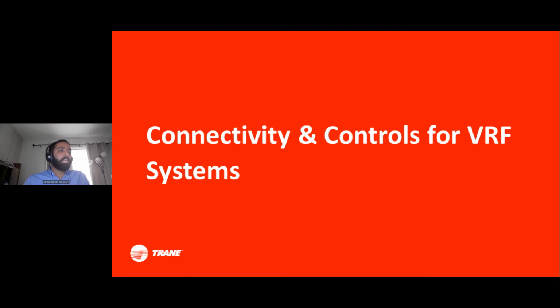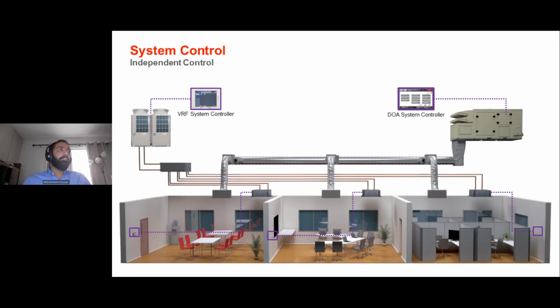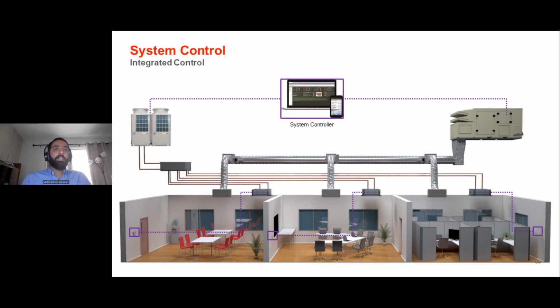Thanks, Scott. So as Scott mentioned, connectivity and controls have become an increasingly important portion of VRF design as the pandemic has progressed. In the past, VRF systems had a reputation for not communicating with traditional BAS systems. So you would have a VRF system that's running independently of the traditional HVAC equipment in the building, and that would typically be the DOAS unit and maybe some ancillary devices. What Trane has done as part of our joint venture over the last few years, we've developed and integrated the Trane Mitsubishi VRF offering into our Tracer SC Plus platform.